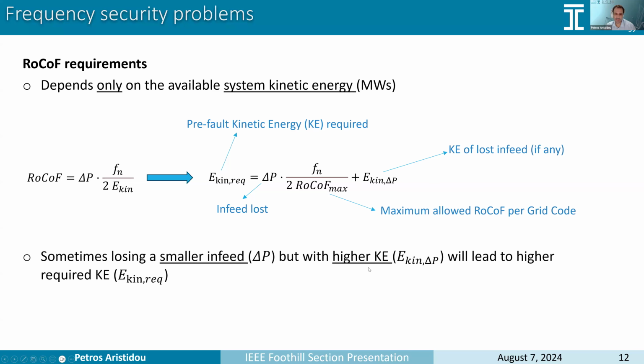Why is this important? Because sometimes the worst case scenario is not losing the largest in-feed. It could happen that we have a generator that provides a lot of inertia in our system, but at that specific point in time is generating a small amount of power. And that could be a worst case scenario, losing that generator, rather than losing a PV park that is generating more power. So delta P is larger, but it does not contribute any kinetic energy to the system. So it's not very straightforward which is the worst case scenario we need to use in order to find the kinetic energy required in the system.